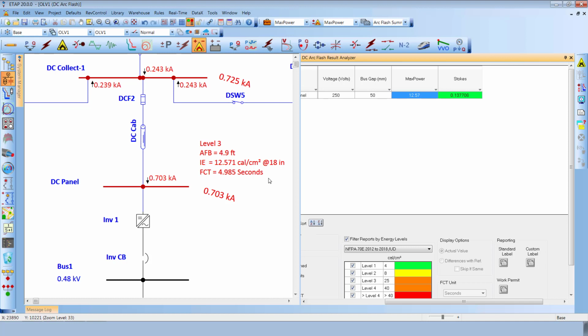Now, the choice of the maximum power method and the Stokes method comes down to the actual available incident energy results and the available PPE that is used for the current location, and the choice of the method involves good engineering judgment to choose between one or the other. In most cases the Stokes and Oppenlander method with the double iteration technique could be more ideal for an application that involves PV arrays and photovoltaic systems.